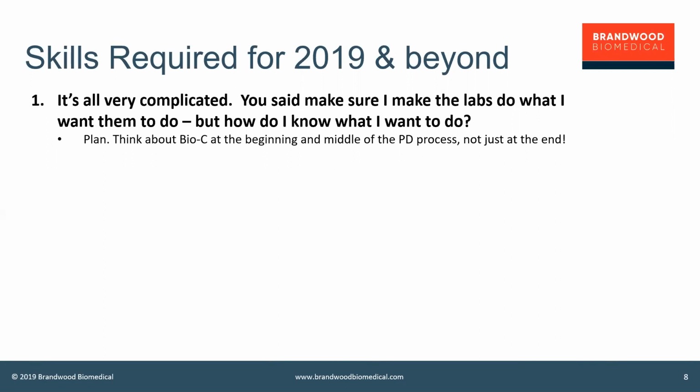These days, you need to have a plan, and the first thing on your plan is going to be work out, of course, what sort of characterization your device has in terms of body contact and contact duration, and then begin to make a plan of how you will evaluate it for biocompatibility.